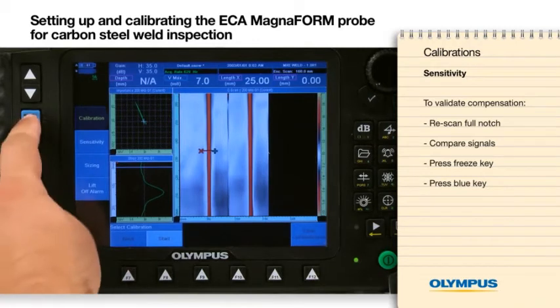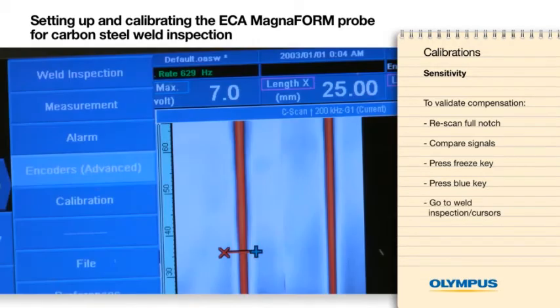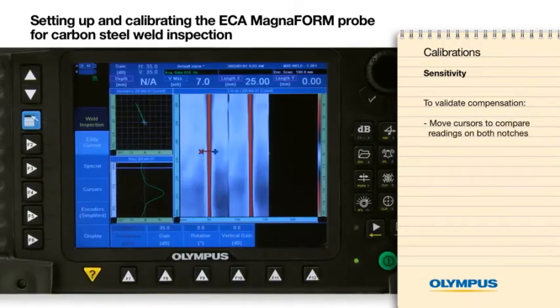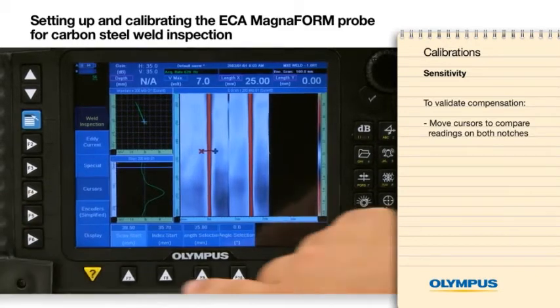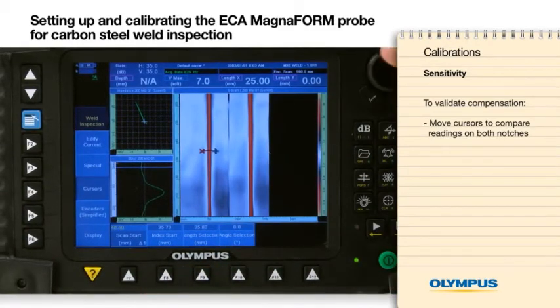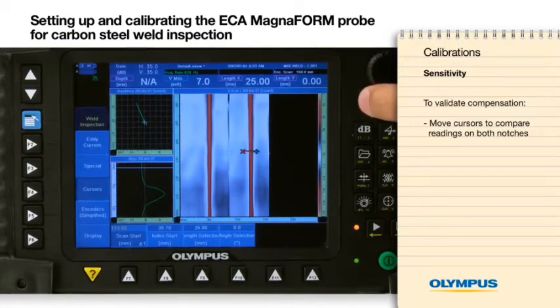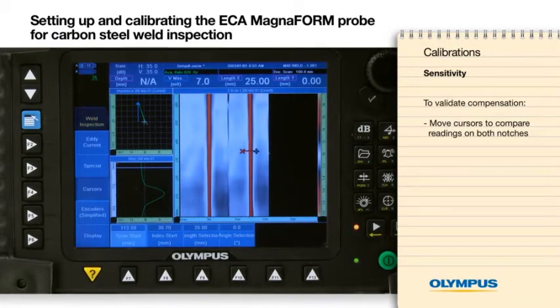Press the blue key, go to Weld Inspection Cursors, and move the cursors to compare the readings on both notches. If the readings are similar, the instrument is properly calibrated. If not, redo the sensitivity calibration.